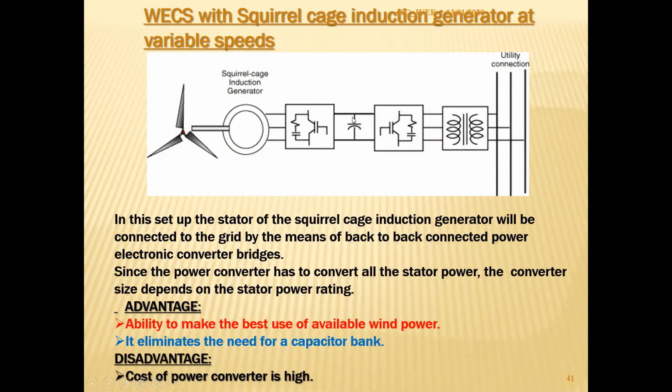fixed frequency AC voltage at the output, and this transformer is for boosting up if the DC bus voltage is not high enough. Then this is connected to the grid. The control action of this one is to supply reactive power, bring active power, rectify it and dump it to the grid. This converter will be operating based on the available information of phase and frequency of this utility connection. At the same time, it will try to fix the DC bus voltage to a fixed value, means you can have a DC bus voltage reference.